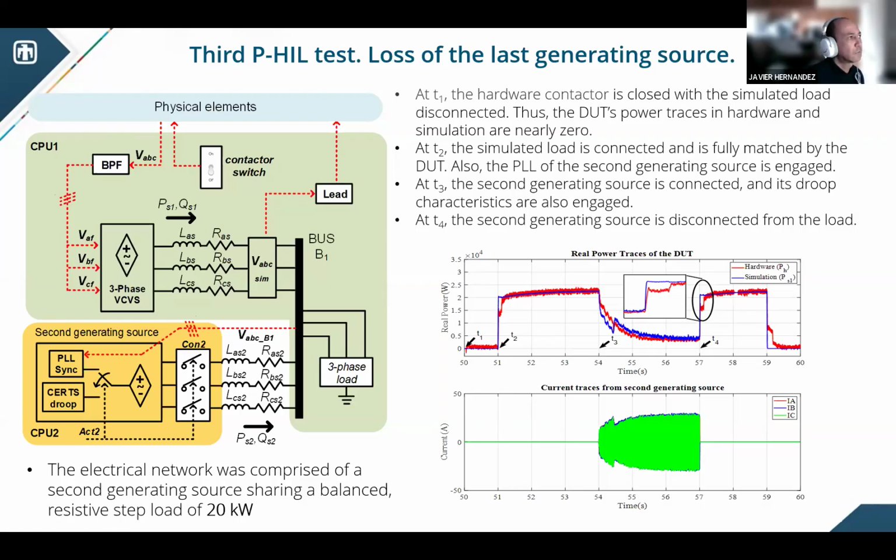This one set the foundation for a second generating source that will be more elaborate in nature. We are working on the design of a model that includes a diesel genset, and we're trying to use some of the parameters of the actual 250 kVA diesel genset that we have here at our facilities at Sandia. The main deliverable this year from Sandia to UNIFI will be a similar test like this one, but instead of using this type of hybrid source, we are going to use an actual model of a diesel genset. We needed to run this test again for safety purposes, and also as a stepping stone towards a more elaborate model of this second generation source, which again is going to be a diesel genset model.